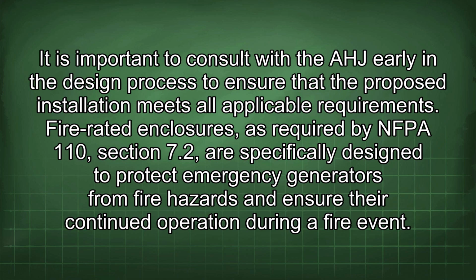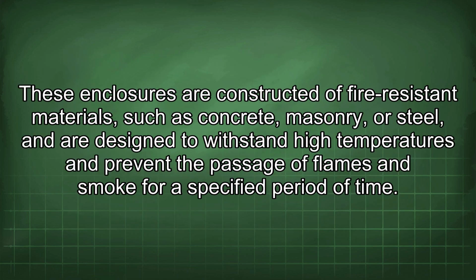meets all applicable requirements. Fire-rated enclosures, as required by NFPA 110 Section 7.2, are specifically designed to protect emergency generators from fire hazards and ensure their continued operation during a fire event. These enclosures are constructed of fire-resistant materials such as concrete, masonry, or steel, and are designed to withstand high temperatures and prevent the passage of flames and smoke for a specified period of time.